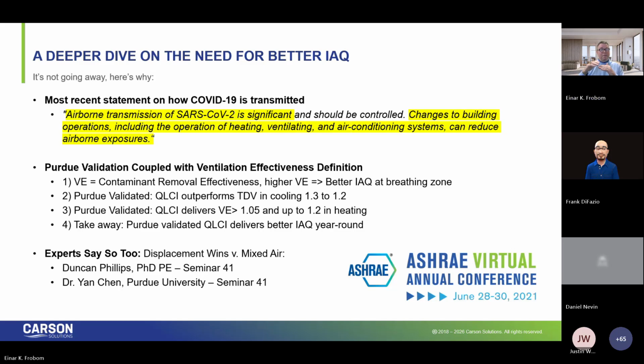Conversely, if you have a ventilation effectiveness defined as greater than 1, that means the air quality being exhausted is 1,000 parts per million in my example, and where the students are in cooling, the default value is 900, resulting in a ventilation effectiveness of 1.2. We got a better air quality where the students are than what's being exhausted. That seems to make pretty good sense to me. So what they proved is that the QLCI actually outperformed traditional displacement ventilation, 1.3 to 1.2. But more importantly, in heating, Purdue validated that our system's ventilation effectiveness was never below a 1, and it went up as high as 1.2. So we're always in displacement, whether we're in heating or cooling. That is a critical component to better indoor air quality, but also energy efficiency.